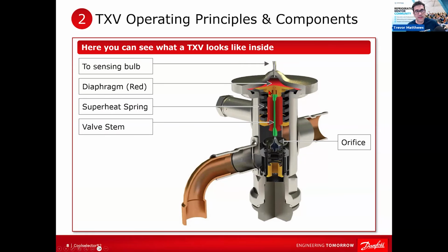Yeah. And the big thing is, if one of those is out of whack, if you don't have any refrigerant in that bulb, we're not going to open, you know what I mean? We've got no opening force. If we have something jammed in it because you didn't use inert gas and now I'm getting carbon stuck in there, it could be jammed open. Keep in mind, these are moving parts, man, and they're small. You can easily draw blood with the valve stem, the valve seat on some of these smaller TXVs. They're that small, so it doesn't take much to plug these up.